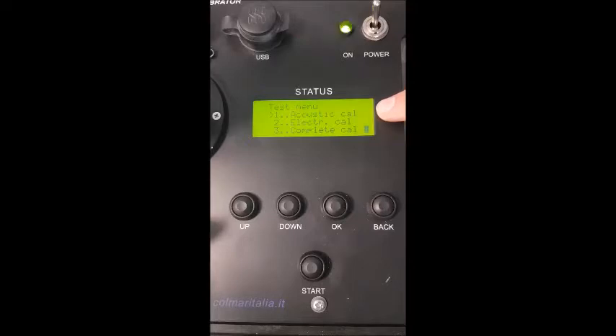Acoustic calibration uses the microphone to produce a sinusoidal acoustic signal that creates a stimulus for the hydrophone, and this stimulus is then amplified by the internal circuitry of the hydrophone, and the electrical signal is then read by the device. The electric calibration instead produces an electric stimulus just for the amplifier circuit. So just the amplifier circuit is being tested, not the piezoelectric ceramic itself. These 2 calibrations operate at different frequencies. The acoustic calibration is limited to 100 Hz to 700 Hz. The electric calibration has a wider range and can go from 3 Hz to 200 kHz. Obviously, the complete calibration combines both.